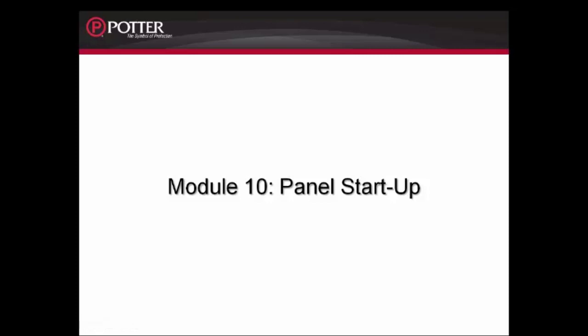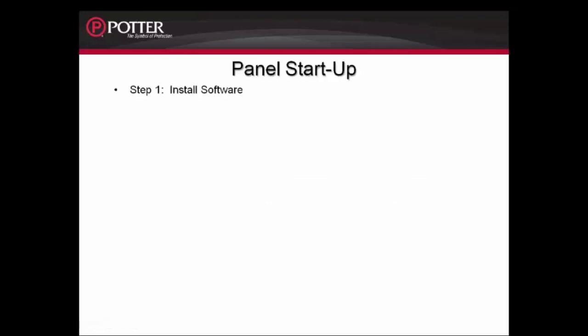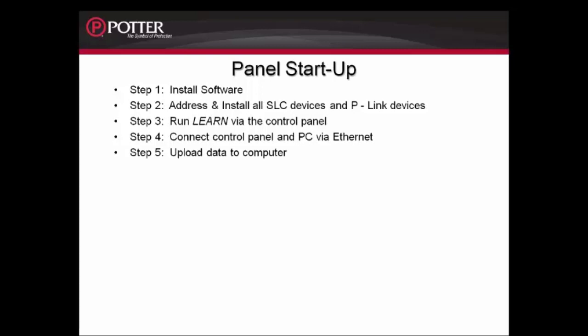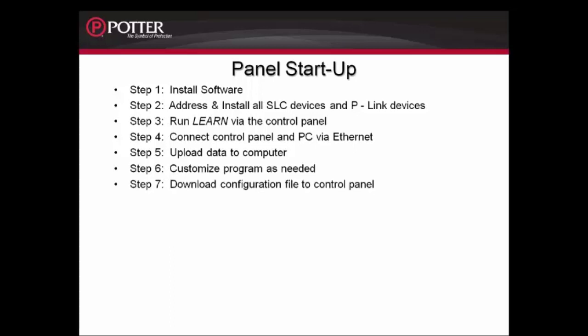Step 1: Install the software. Step 2: Address and install all SLC devices and P-Link devices. Step 3: Run the Learn via the Control Panel. Step 4: Connect Control Panel and PC via an Ethernet cable. Step 5: Upload the data into the computer. Step 6: Customize the program as needed. Step 7: Download the configuration file to the Control Panel and test the system.